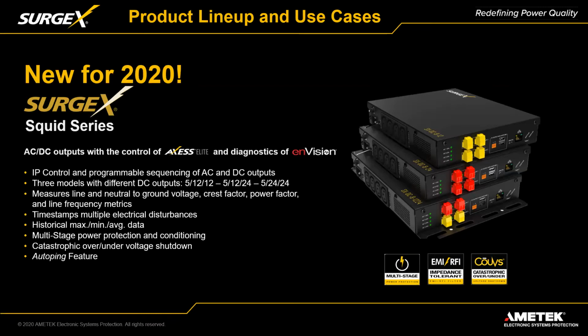It's remarkable because we've taken some of the control features of the AXESS ELITE. It has an IP port that allows for remote control, with the completely programmable sequencing of the AXESS ELITE. The sequencing can take into account both the AC outlets and the DC outlets. The beauty of having the DC power supply on there is you can get rid of those external power supplies, which are low cost and not very robust. I'm sure you've come across the fact that when troubleshooting, a lot of times it's the external power supply that's the issue.